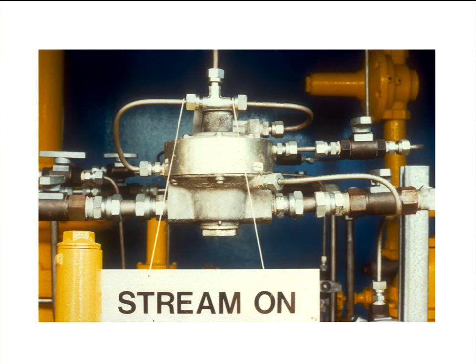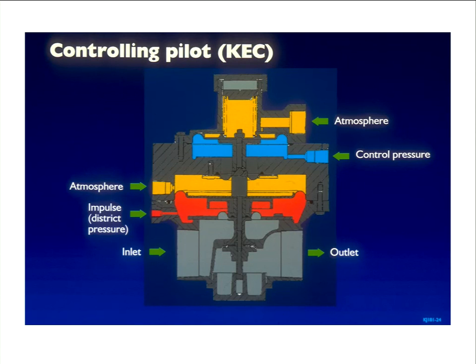So that's an electro pneumatic converter. Contrast doesn't show up well, but that's like an I to P controller in a cabinet. And again, because it's electric equipment in a gaseous area, you've got to look after it. In this case, I think they adopt an intrinsic safety approach. So what you do is you minimise the possible energy that can occur. I don't know if you've ever noticed, sometimes if you switch a light, you can generate a spark.